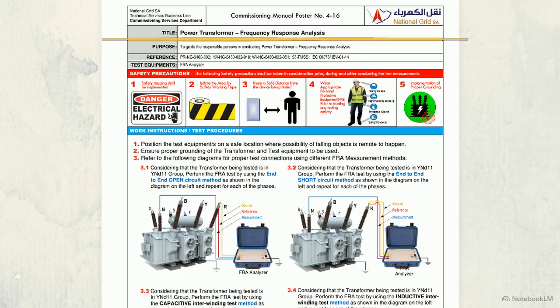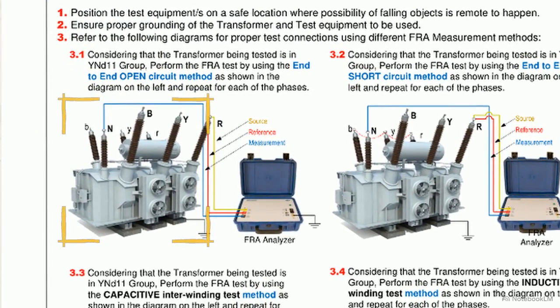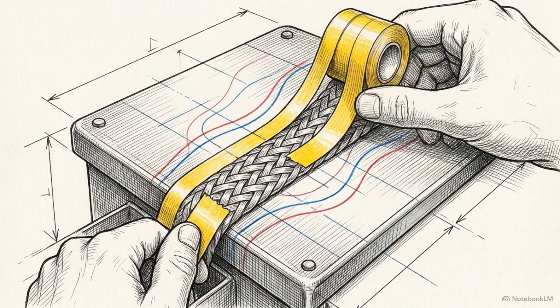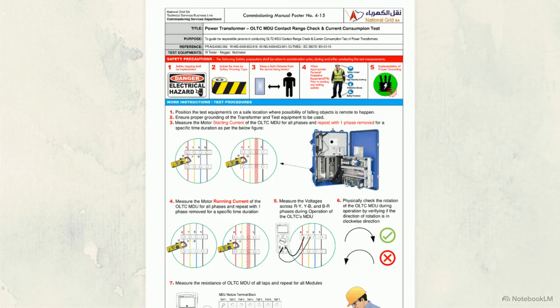Using the specified end-to-end open and short circuit measurement methods, we send a frequency sweep through the windings to establish a baseline signature for detecting core or coil movement. Because high-frequency signals are highly sensitive to stray capacitance, test lead routing and grounding lengths must be perfectly repeatable to avoid generating false diagnostic signatures. Moving to dynamic systems, this testing manual outlines on-load tap changer checks.